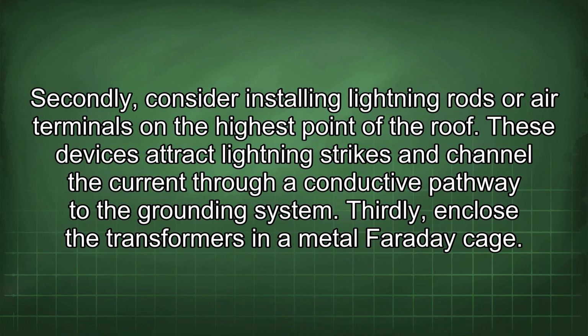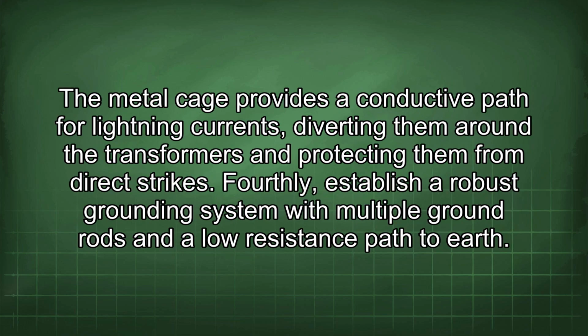Secondly, consider installing lightning rods or air terminals on the highest point of the roof. These devices attract lightning strikes and channel the current through a conductive pathway to the grounding system. Thirdly, enclose the transformers in a metal Faraday cage.